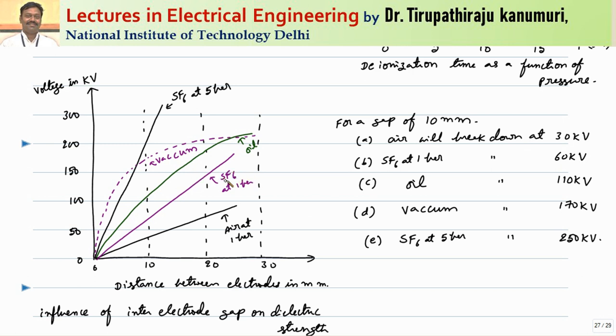If you take SF6 gas at normal atmospheric pressure, it will have better characteristics than air — a dielectric strength of up to 60 kV. But if you increase the SF6 gas pressure up to 5 bar, it can withstand up to 250 kV with just a 10 mm gap between electrodes. That is the advantage — just 1 centimeter separation gives a dielectric strength of around 250 kV. For oil, we get around 110 kV per centimeter, which is far greater than air but less than SF6 at high pressure.